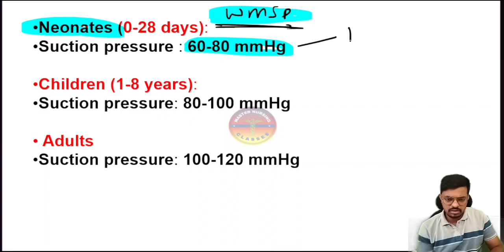Yes, I have told in the last class. Anyone want to answer the suction pressure in the preterm unit? Fatafat. Already told in the last class. Yes, very, very good. Okay, that is 40 to 60 mm of Hg, the suction pressure we have to keep in the preterm unit, and for the term unit is the standard pressure, that is 60 to 80 mm of Hg. Okay, so when the examiner mentions children in the question, if he mentions the suction pressure in the children, the answer will be 80 to 100 mm of Hg, right? So this is the standard suction pressure we have to apply to the children.